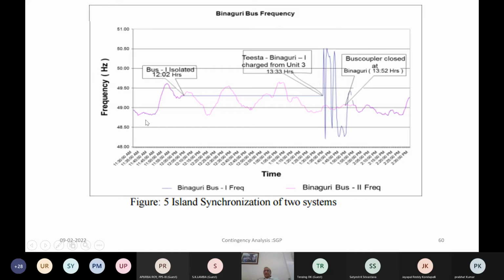And when you suddenly change the frequency very widely, here the frequency is almost 48.5 and up to 50.5. You can see the fluctuations. Whereas in the islanded mode of operation, the frequency is in the band of 49.5 to about 49. So these are the sort of fluctuations. So with a governor operating in isolated grid mode, it's possible to achieve this type of stable frequency.